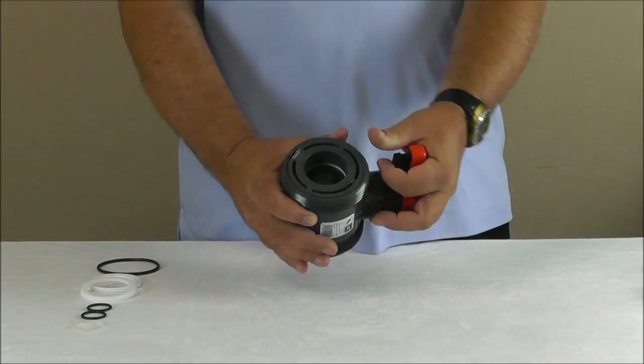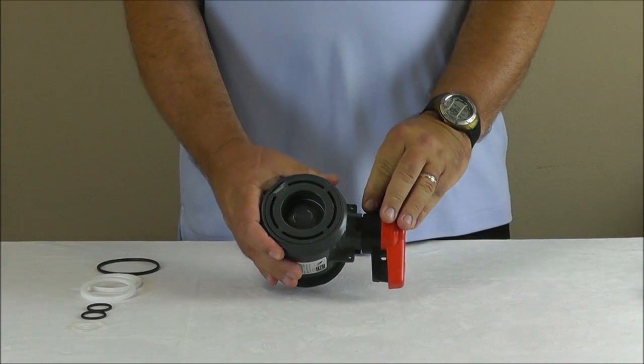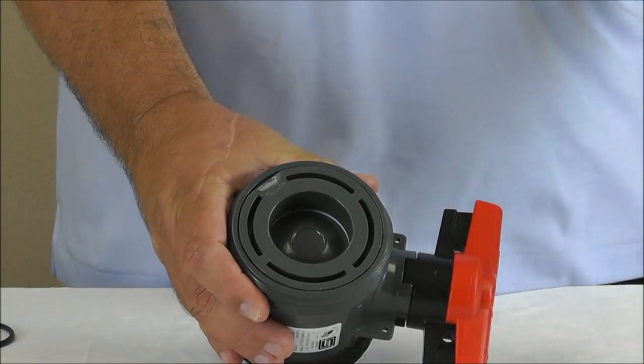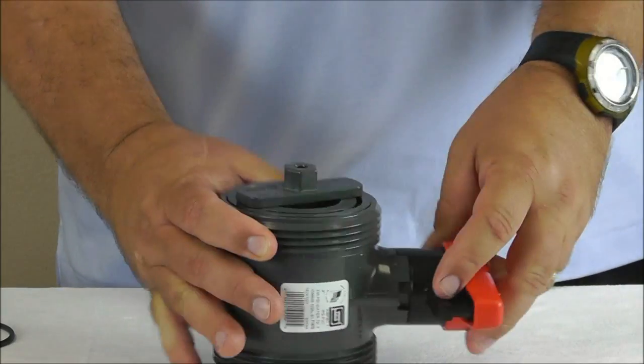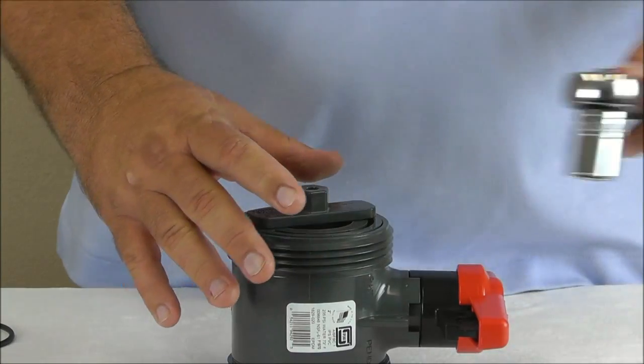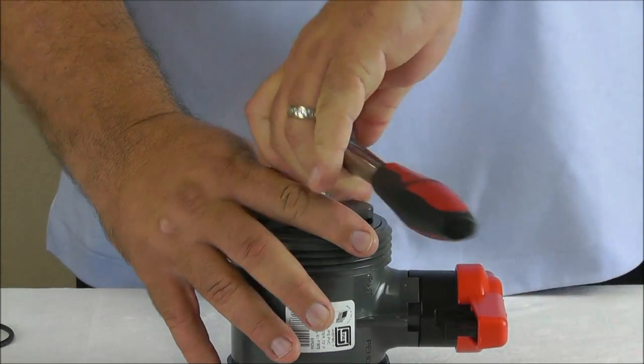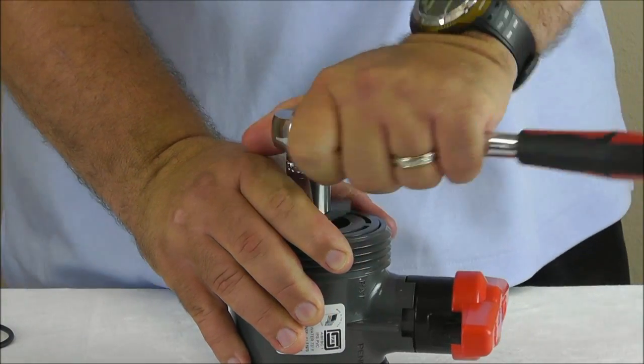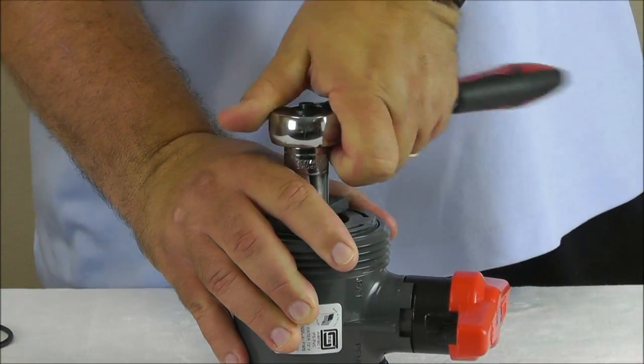Next, turn the valve into the closed position. Insert the seal carrier tool that came with the valve into the slots and using your three quarter inch wrench, unthread the seal carrier counterclockwise while holding the valve body firmly in place. If you no longer have the seal carrier tool, it can be ordered separately along with the seat and seal kit.